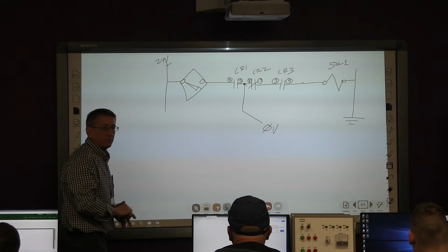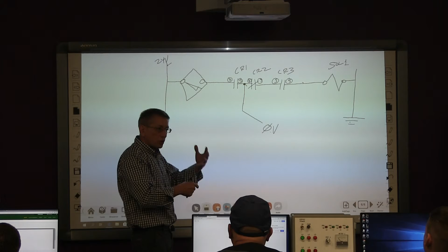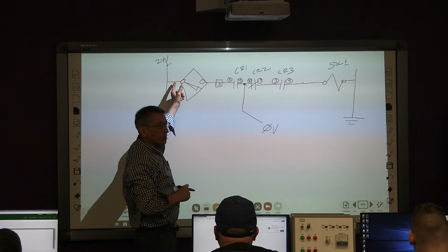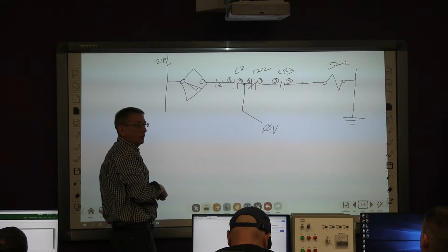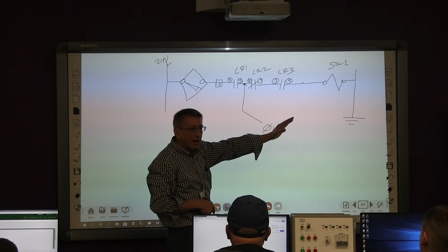Another thing about your electrical prints, which are your roadmap - very good clue, they have labels. Any external devices, external from the main electrical panel, what do they have to do? They have to come into the panel and land on a terminal strip - the wiring by code has to land there. So your drawings should have a terminal number where this thing's terminated in the panel. You open the panel, you see all the terminal strips, the terminal block. Look in your drawing - we haven't even gone out to this switch yet, we don't care yet. Now we measure up to this point - the terminal block, the terminal strip it's coming in on. So you've eliminated everything inside the panel, pretty much.